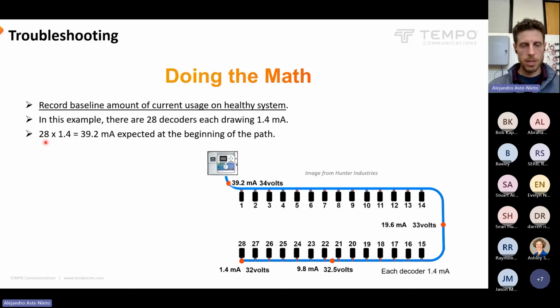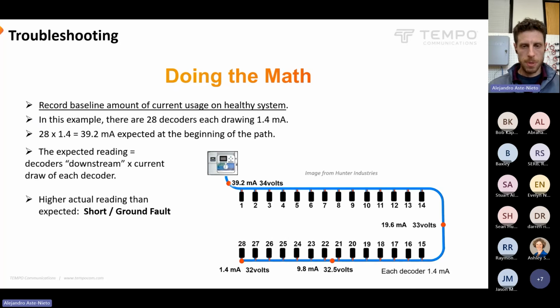But let's say we don't have that baseline number, we can do this math. We can say 28 decoders, 1.4 milliamps each, we should have roughly 39.2 milliamps consumed on this entire wire path, coming out of the controller, and take a measurement there. So when we take readings, it's the amount of decoders downstream times the current draw of each of those decoders. Here we're halfway, so we want 19.6 milliamps on our clamp meter when we're clamped around the wire.